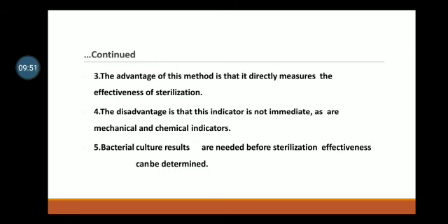The advantage of this method is that it directly measures the effectiveness of sterilization. The disadvantage is that this indicator is not immediate as are mechanical and chemical indicators. Bacterial culture results are needed before sterilization effectiveness can be determined.